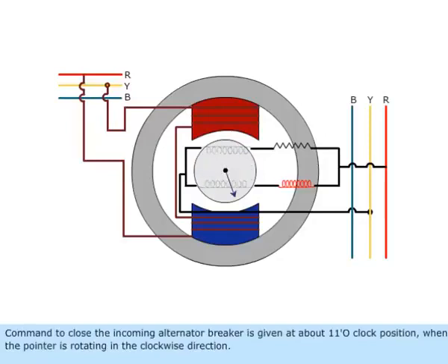The command to close the incoming alternator breaker is given at about 1 o'clock position when the pointer is rotating in the anticlockwise direction.